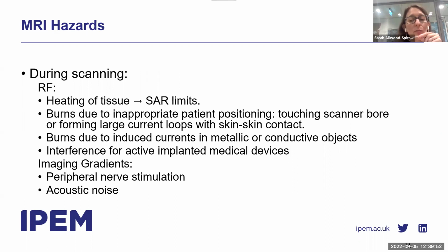Even within the SAR limits, there are several ways that inappropriate positioning of patients could cause the patient to be burned. If any part of the patient's body is touching the sides of the bore, this can result in a burn. If there's skin-to-skin contact within a large current loop within the patient, so for example, the patient's hand touching their thigh or the patient's knees touching together, which could create a current loop around their legs, that point of high resistance where the knees are touching can result in a contact burn at that point. We also have the possibility of any metallic or conductive objects in or on the patient, depending on the size and shape of these, heating significantly due to induced currents and resulting in a burn. And this is a particular concern for implanted medical devices that have long leads.